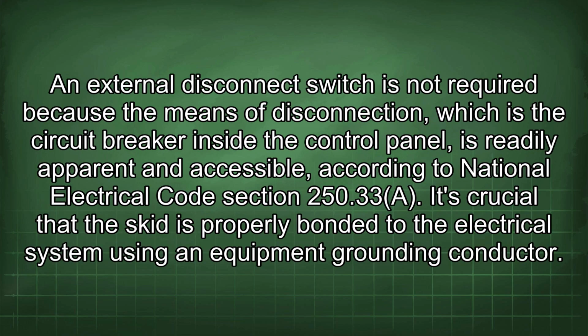An external disconnect switch is not required because the means of disconnection, which is the circuit breaker inside the control panel, is readily apparent and accessible according to National Electrical Code Section 250.33a. It's crucial that the skid is properly bonded to the electrical system using an equipment grounding conductor.